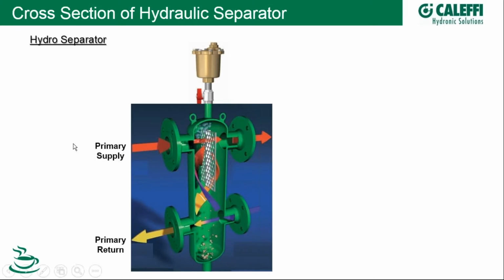So what's going on is we have on our primary side, let's say in the case of a heating application, say from a boiler or a heat pump, we've got heated water coming into our separator and returning back to the boiler. So this is our primary loop. Then over here, we have our secondary supply. Now you're wondering, your eyes are drawn to all this color going on here, and you go, well, that's a lot of stuff going on in there. Well, there's a little bit going on there. Let me just walk through it.